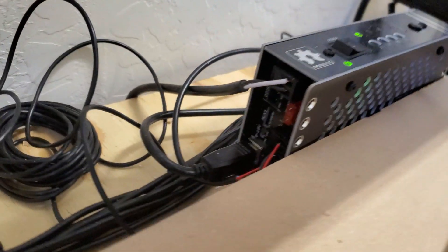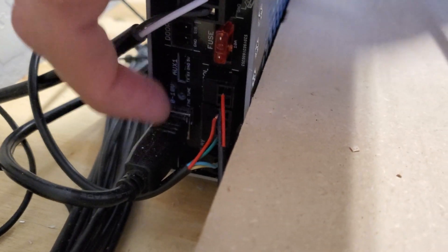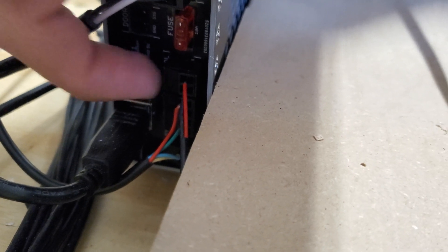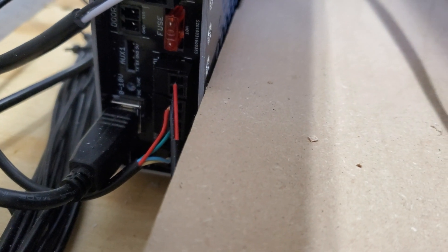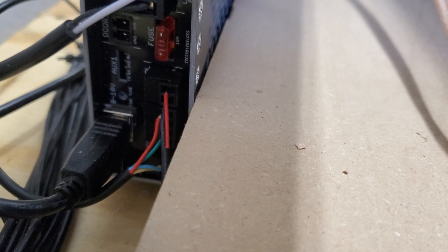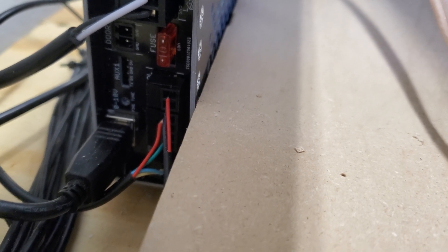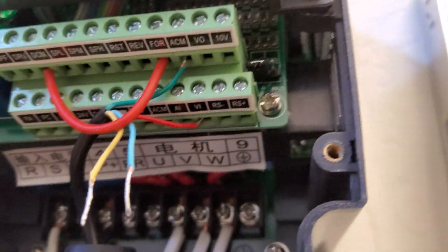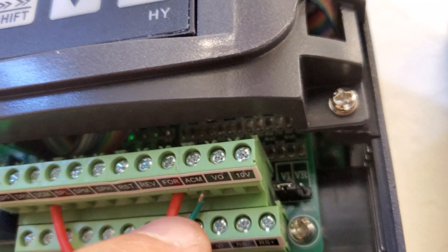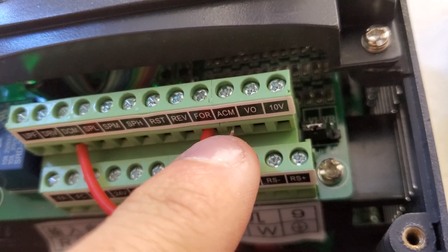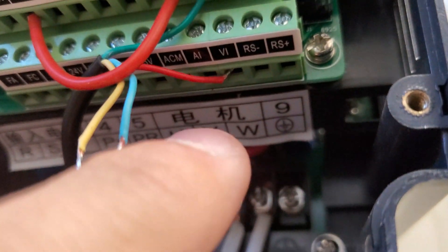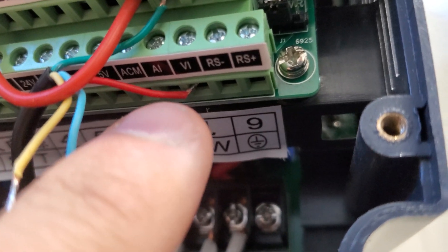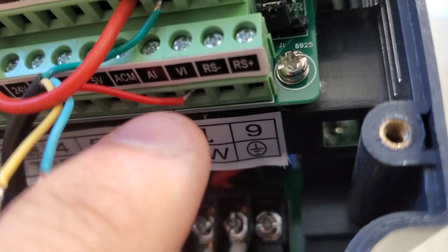That information's passed off using a 0 to 10 volt signal that comes off of the tooling port on the backside of the black box. So you can see that right here. It's a four port connection. You're only using the two outside ones, the ground and then the 0 to 10. The two in the middle you don't use. So you'll run those through there, and then run them up into here. So my green wire is the ground wire, so that goes into ACM. Red wire is the 0 to 10 signal, and that goes to the VI.